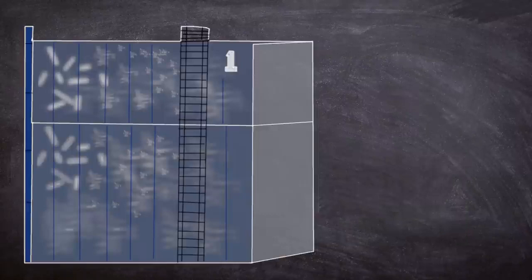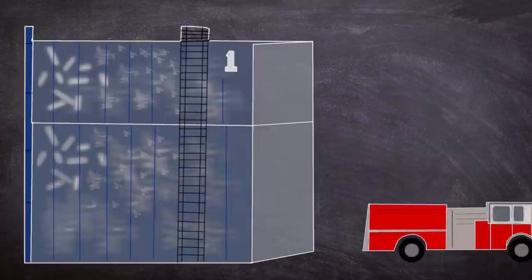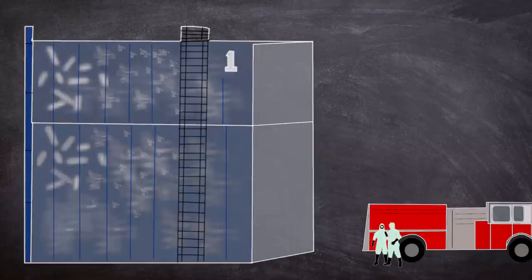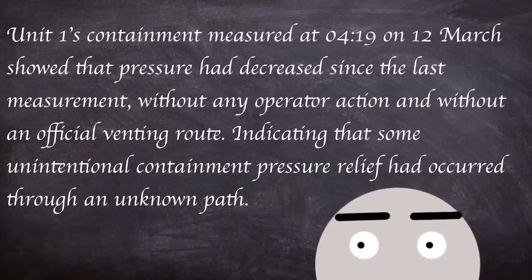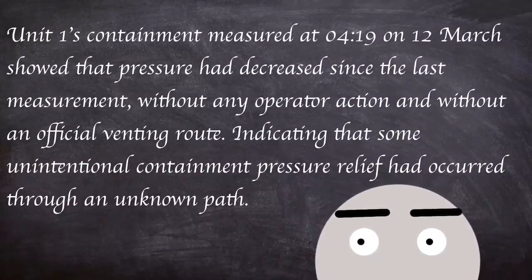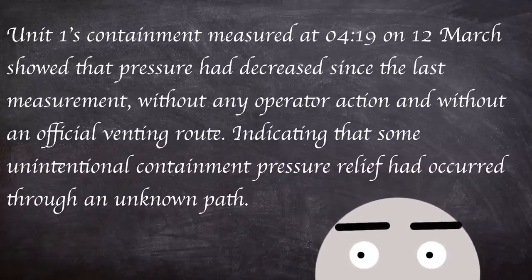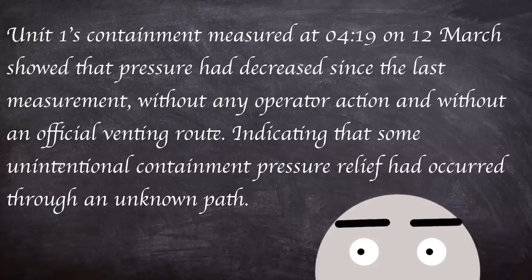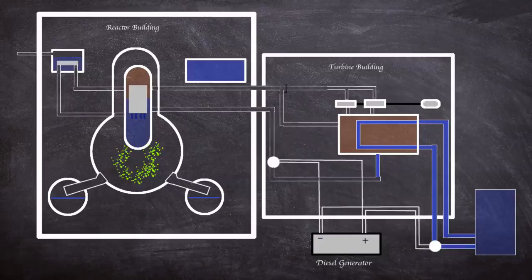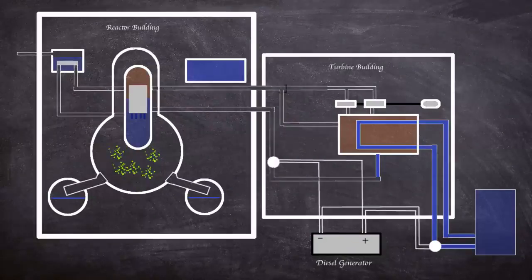At 4 am, an alternate cooling system was put into operation using fire trucks pumping seawater into unit 1, as vessel pressure had reduced. Unit 1's containment measurement at 4:19 am showed pressure had decreased without operator action and without an official venting route, indicating unintentional containment pressure relief through an unknown path. This, coupled with increased radiation levels, hinted at reactor vessel damage.